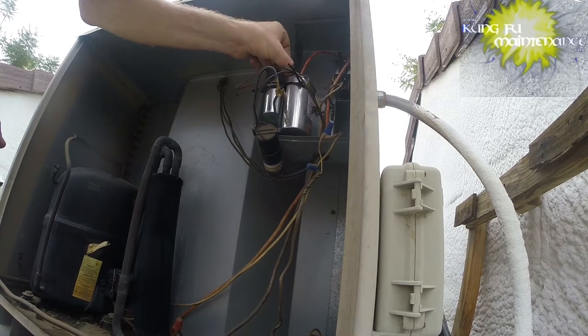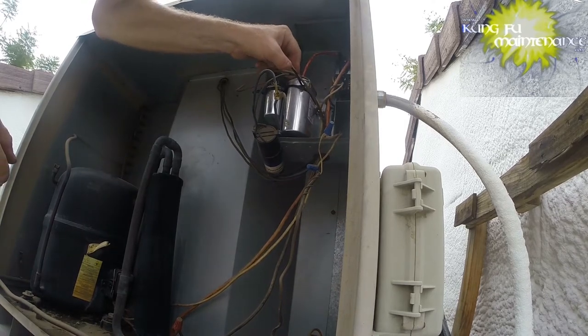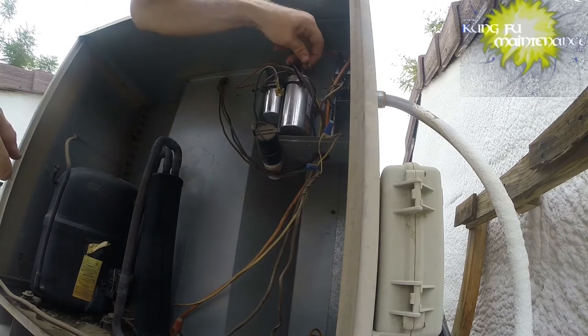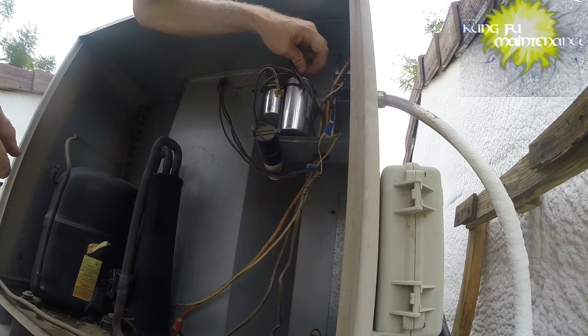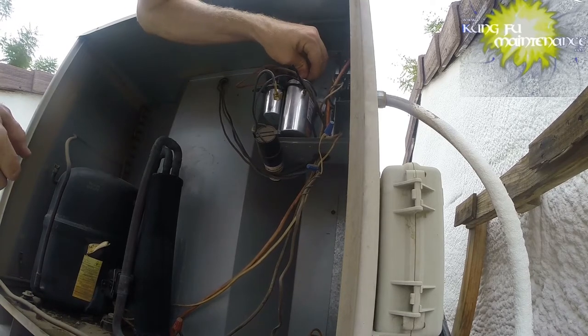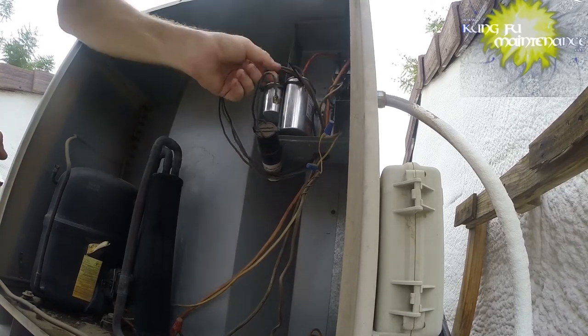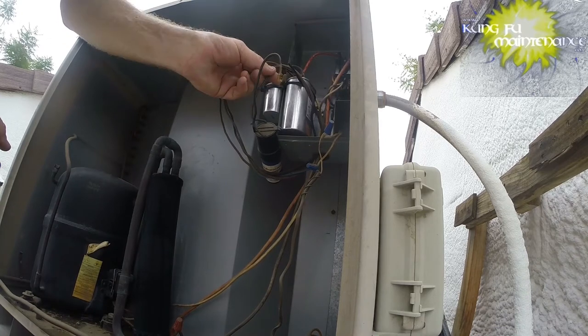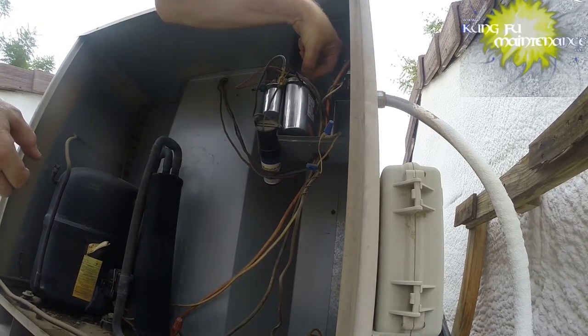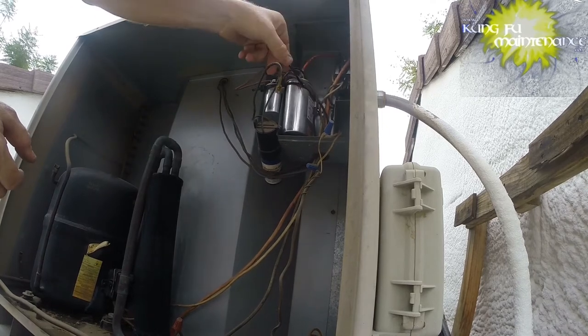I've been hearing about it for some time, and so I wanted to get into it today to test the formula, which is 2650 times the full load amps, which is the running amps, if we're using a hard start kit, which I like to use, divided by the voltage. Lead each side, Herm and common. One lead to Herm.